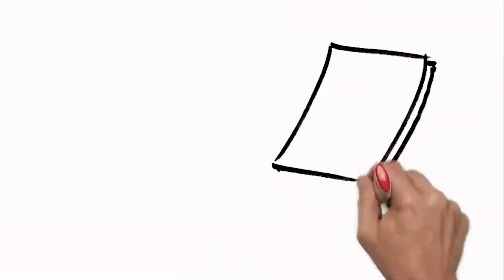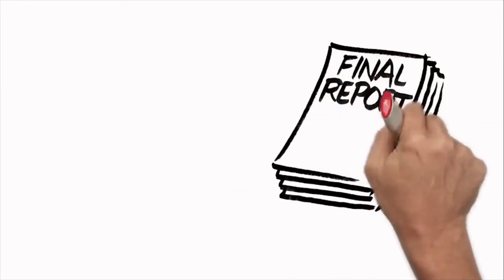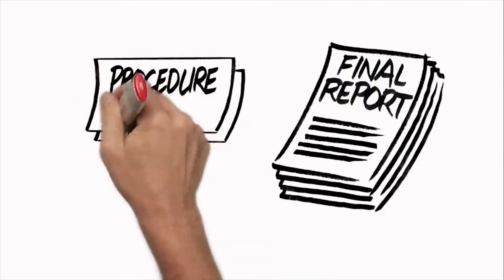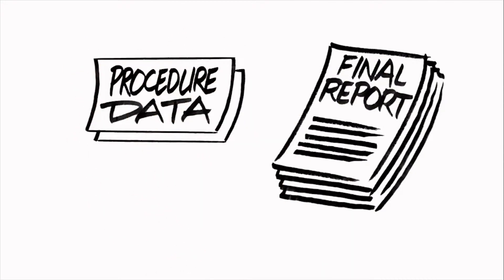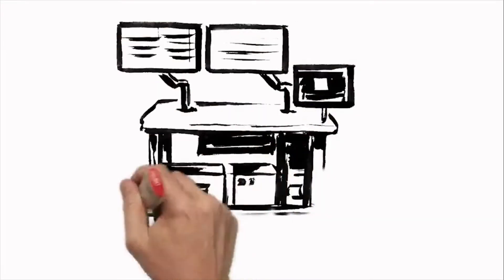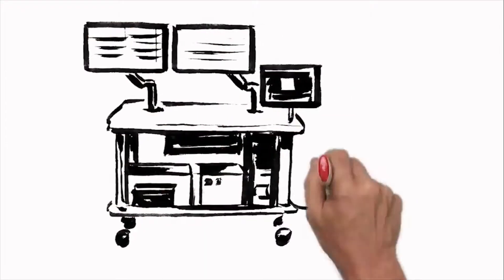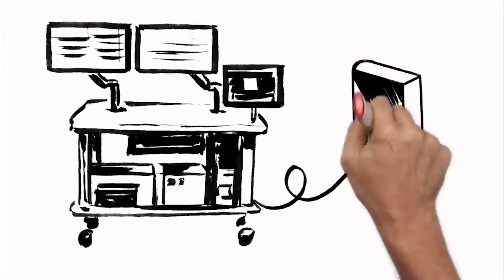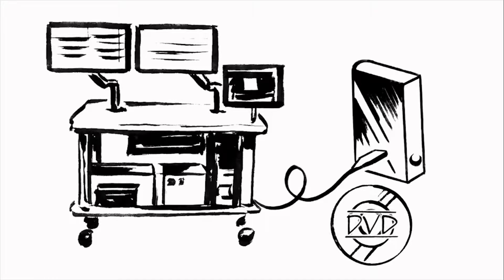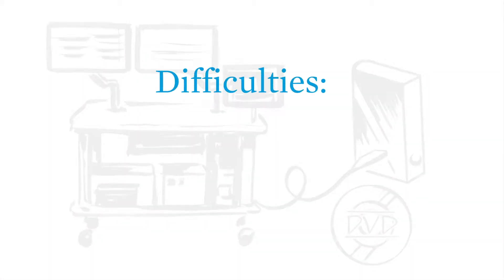Upon completion of an EP case, the final report and the procedure data that has been collected throughout the case can be exported in several distinct ways. Reports and data can be transferred from the Workmate Claris system directly through USB to an external drive or burned to a DVD. While these are simple solutions, they can make it difficult to find archived cases, export the case and securely store patient information. They also may not meet the hospital IT data security requirements.